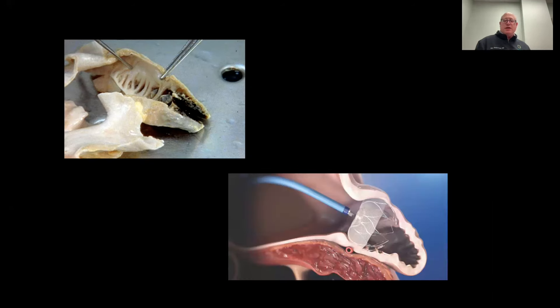This cadaver image shows the same phenomenon — a black blood clot seen when opening up the left atrial appendage in a patient with a history of atrial fibrillation. What we like to do is exploit this anatomy and seal off, wall off, or fence off this area using percutaneous catheter technique, preventing any blood clot that might form from passing into the main left atrium and then to the rest of the body. The device that has been FDA approved for this purpose is called the Watchman.